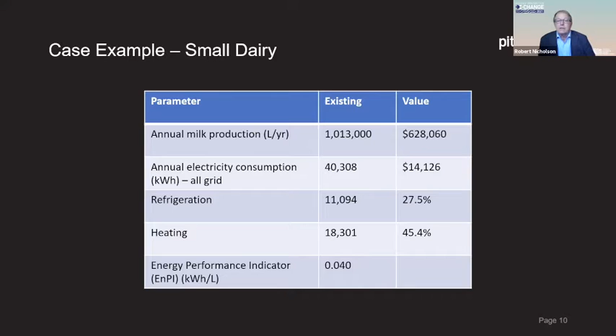In the dairy industry, literature suggests it should be about 0.047, so you might say this farm's operating pretty well, so why change? But as we said, the systems here are at capacity, a larger herd size and milk output is already underperforming in reality, and those things aren't really an option with the current refrigeration plant setup. Looking to change those things allows us to bring in innovation, which will reduce that energy performance indicator and provide a more productive use of the energy being supplied.